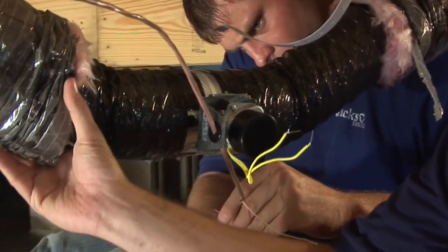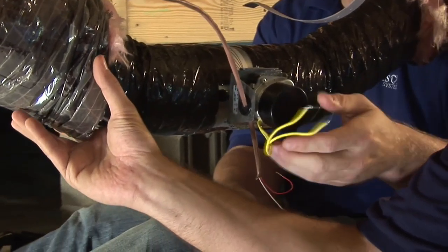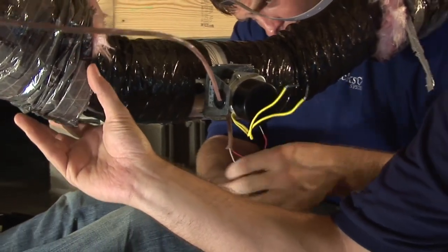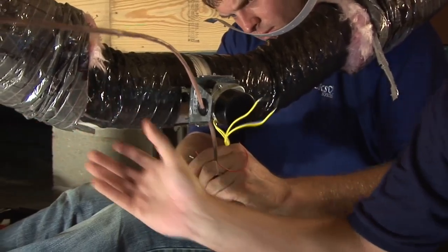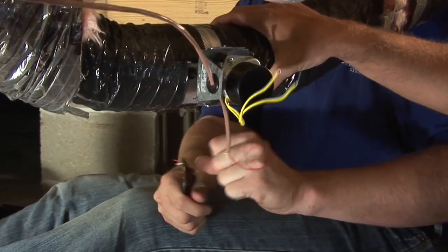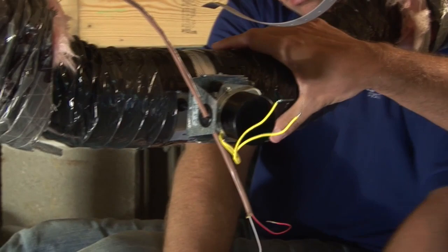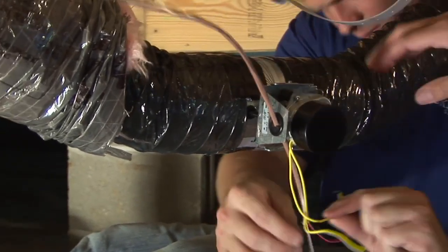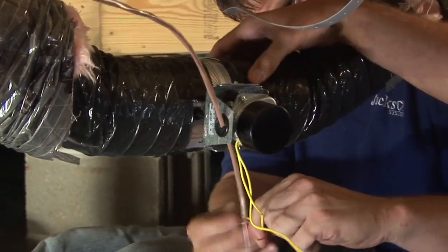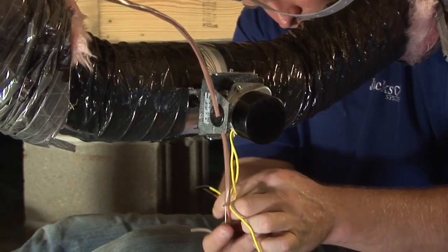As you can see here, we've taken the ductwork, which happens to be flex duct, we've separated that, cut that in half, and we've inserted this round zone damper here. And Ryan has already attached this to both ends of the flex duct and sealed that back up nice and tight so that we don't have any loss of airflow.